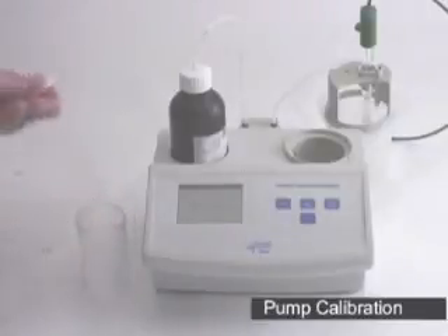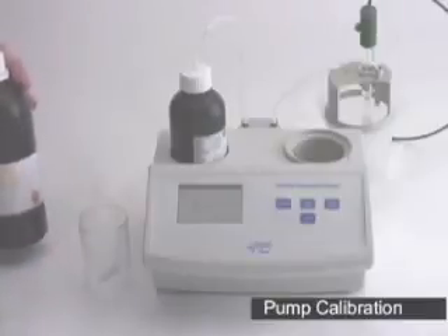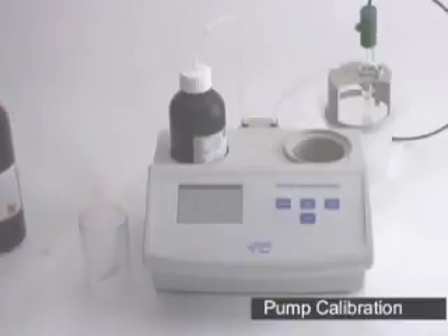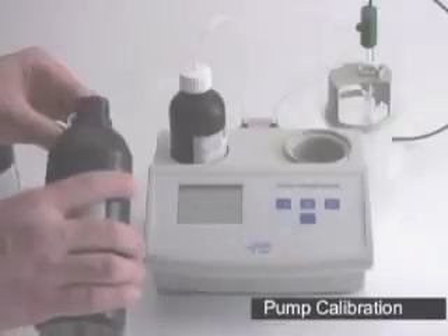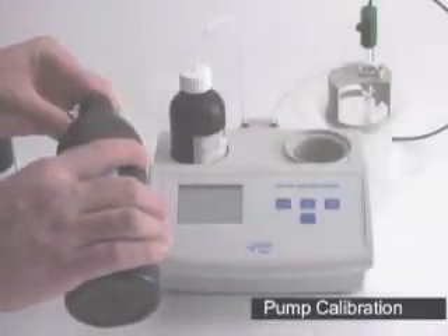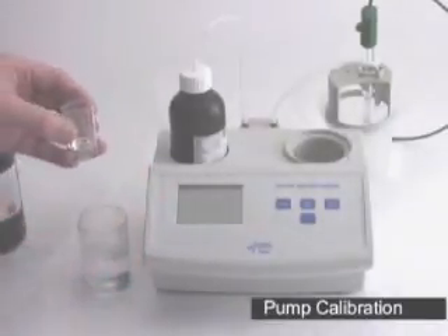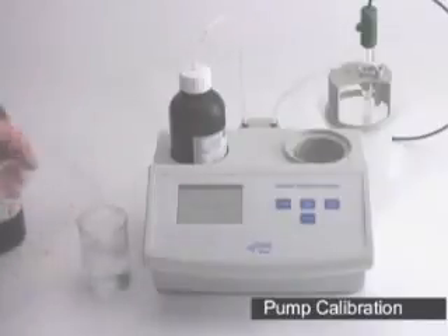Take a clean beaker, add your stir bar. We're going to take the 84-100-50 calibration standard, measure 50 milliliters, preferably with a pipette or a graduated cylinder, and place into the beaker. Take your HI 84-100-53, using the small beaker provided, fill it up to the 5 milliliter line. Volume is not that important, you do not need a pipette. Take the 5 milliliters, dump it into your sample.